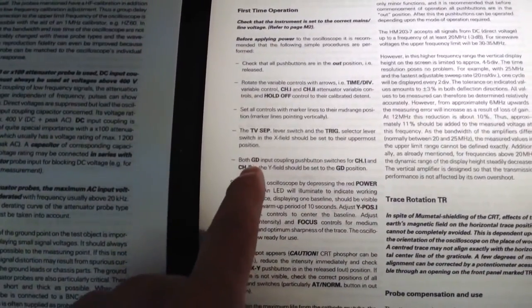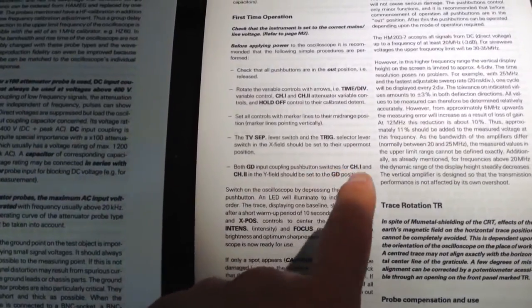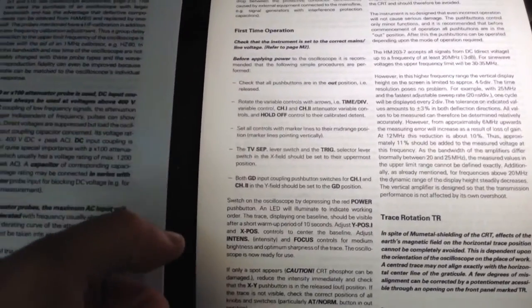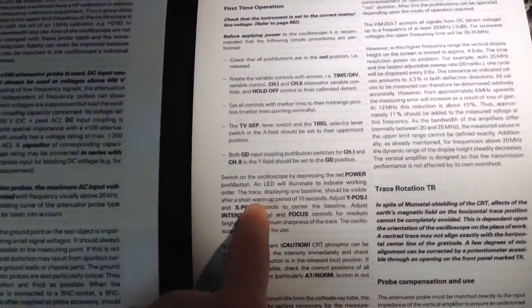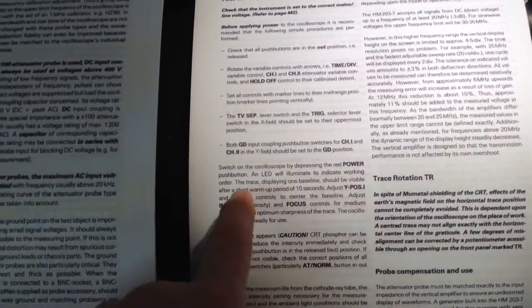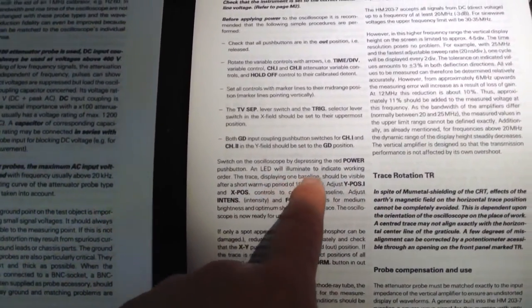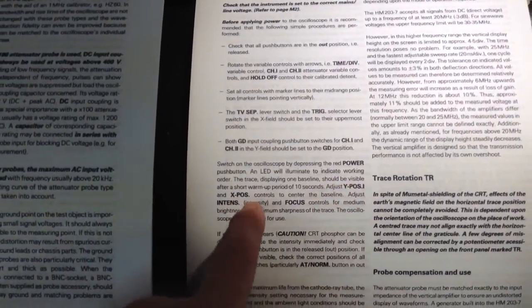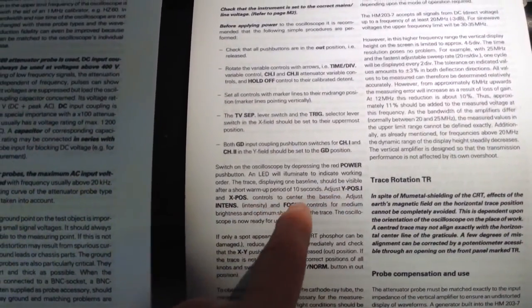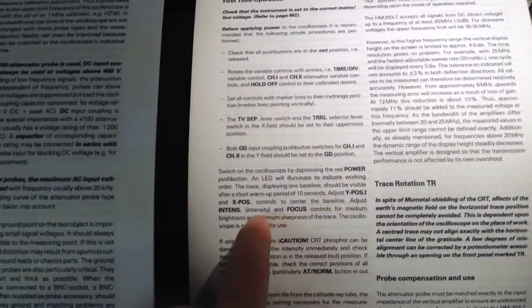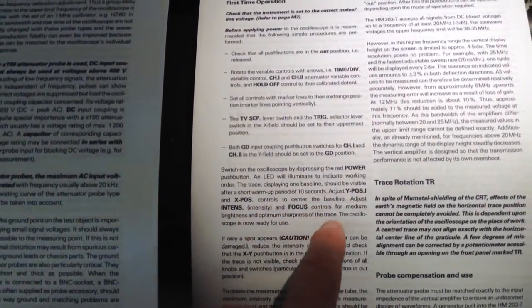Switch on the power button, LED will illuminate. Trace display in the baseline should be visible after a short warmup of 10 seconds. Adjust the Y position, adjust the X position control to center the baseline, adjust the intensity and focus for optimum sharpness.